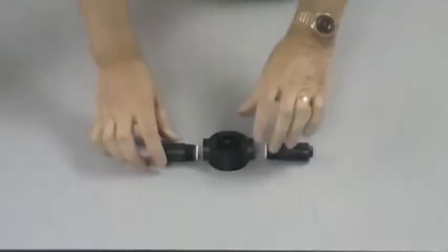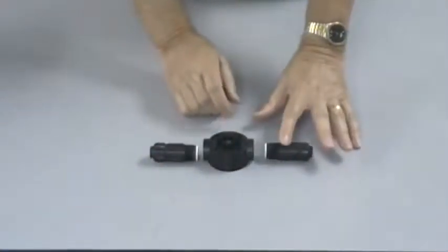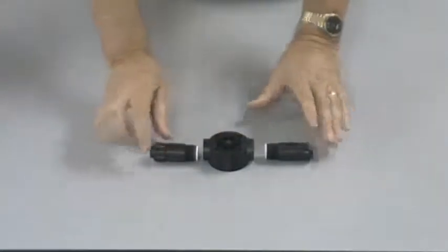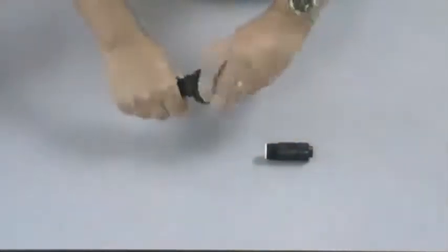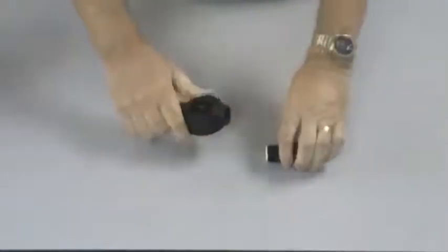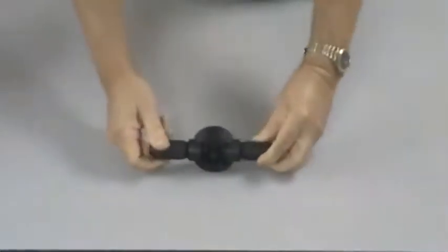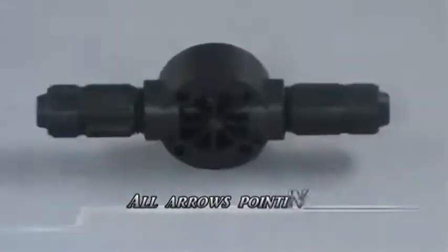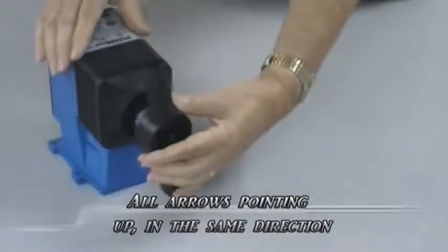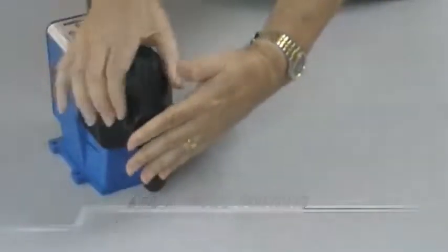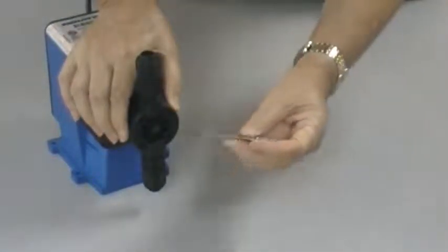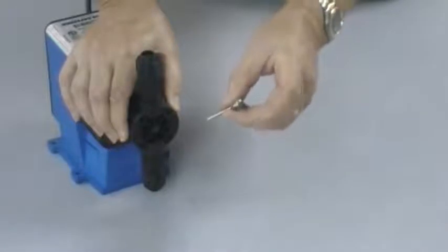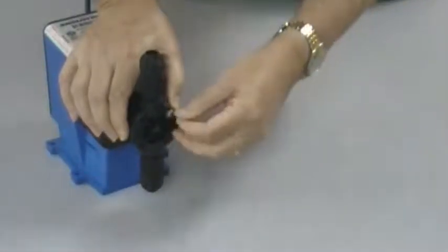Now we will assemble the pump head assembly: the suction valve, the pump head, and the discharge valve. All 3 of these parts have arrows on them that indicate the direction of flow. Now we will install the pump head to the pump. We place the head on the pump with the arrows in the direction of flow. Take our screw, add a washer to the screw head, and insert it into the pump.